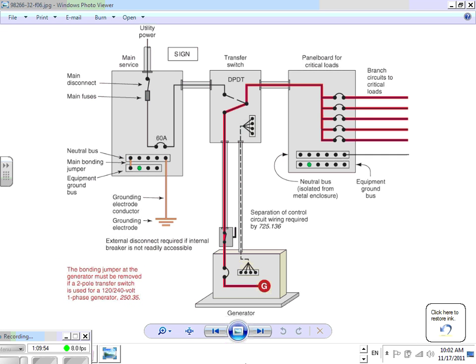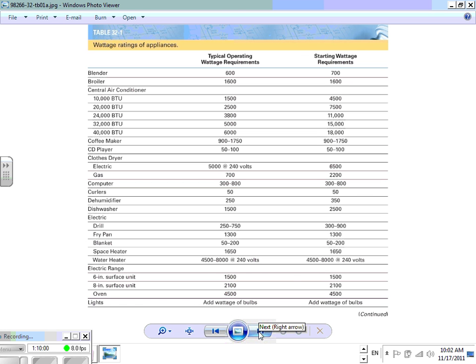Okay, the last thing I wanted to talk about, guys: how do we size generators? Well, there are two ways of sizing generators. One way is to do it by hand, which we would never do. The second way, next time with your friend Chad, you're going to do two softwares. One coming from common software that we have. With common software, guys, you take all the loads that you need to back up. In our case, it's going to be all the loads in the building. Plug them into a software, and the software will do two calculations. It will calculate based on two things.